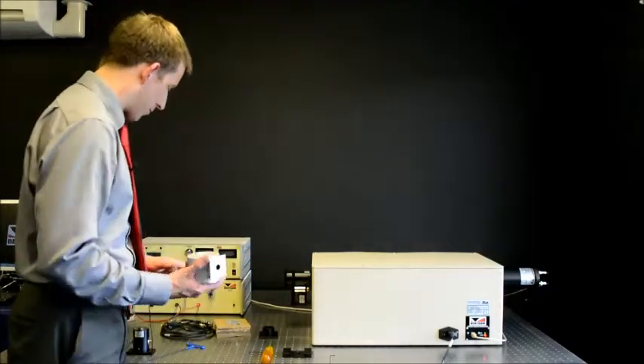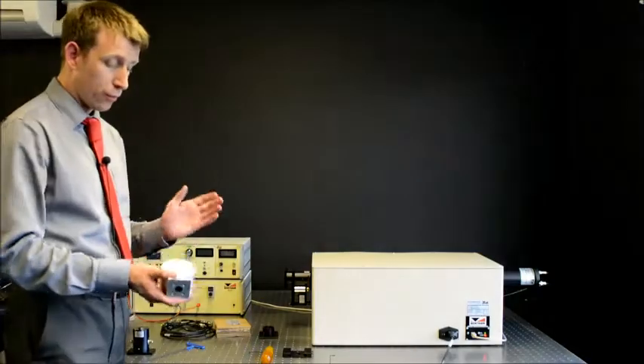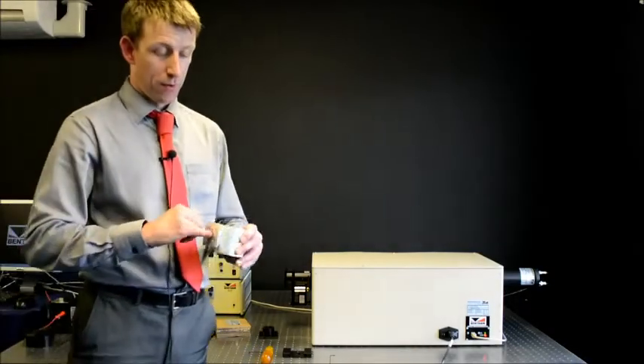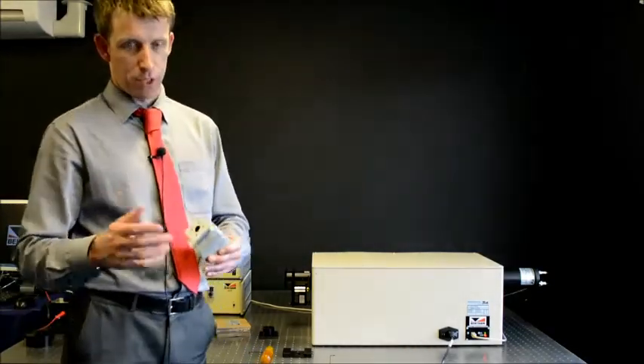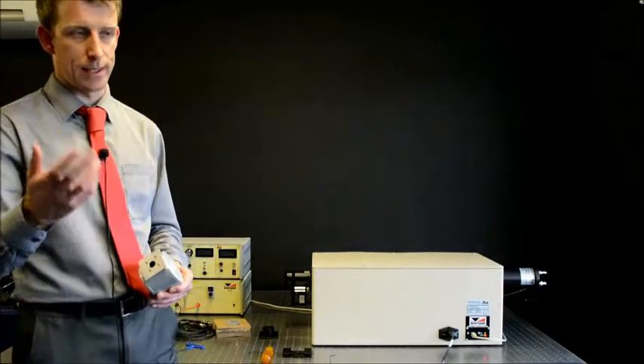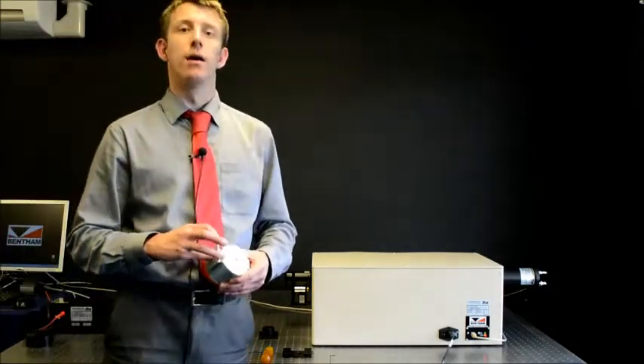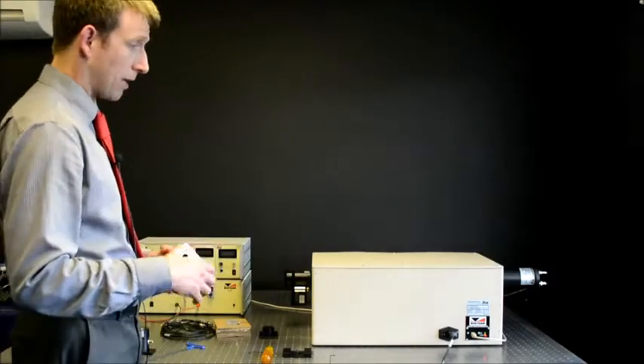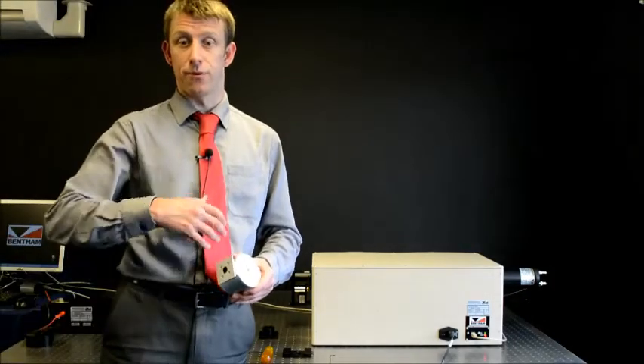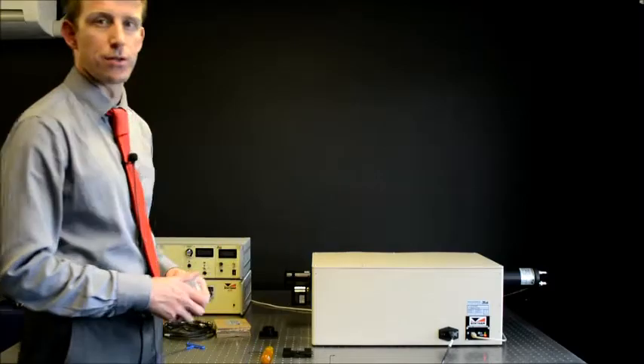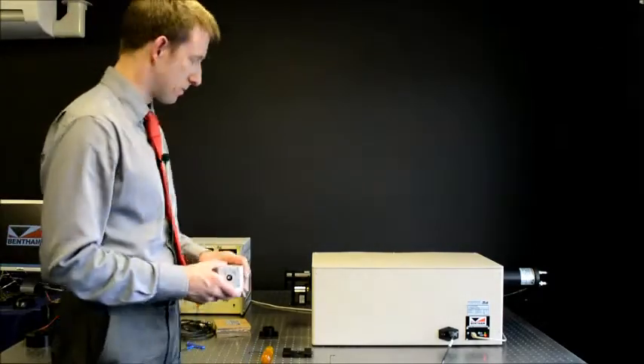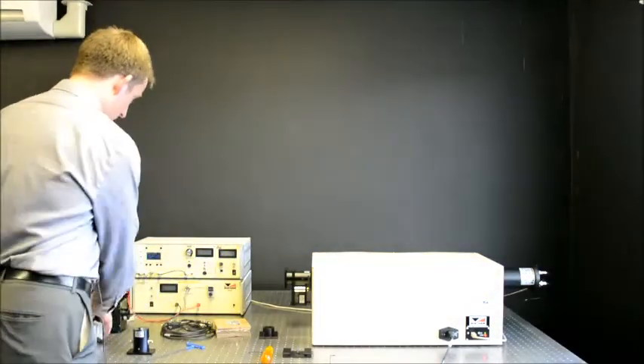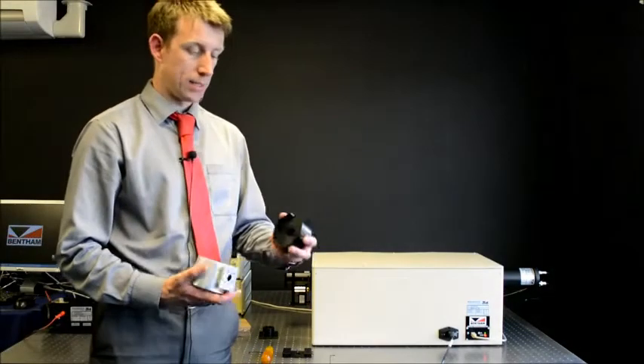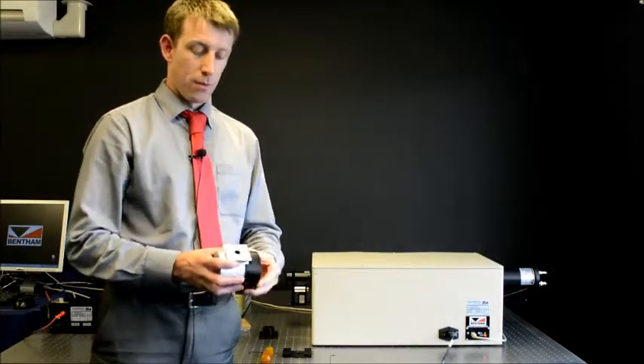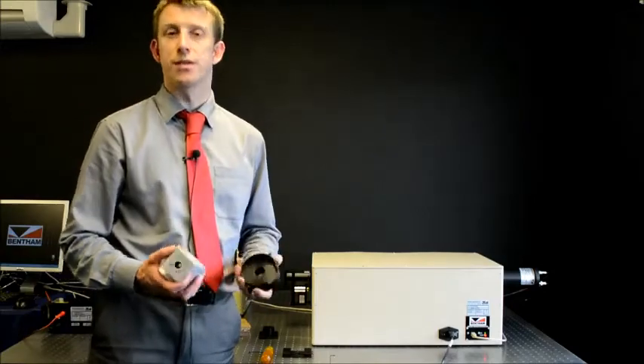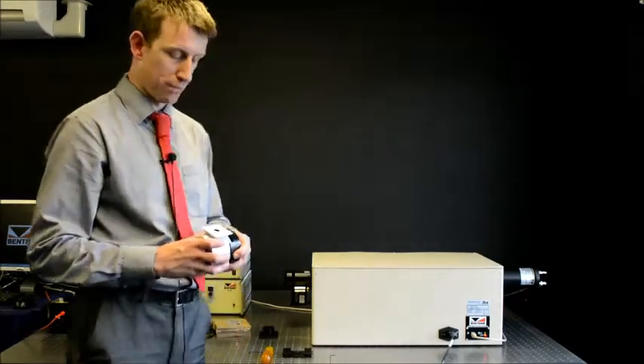So I would certainly recommend avoiding the use, although it can be used with the FOP UV for some measurements above 1100 nanometers, paying attention of the 1380 quartz absorption. And one can also purchase a glass fibre bundle for extending the measurements, certainly up to the range of InGaAs 1700 nanometers. This D8 has also an adapter ring which will attach to the front face of the CL6 for the purposes of calibration.